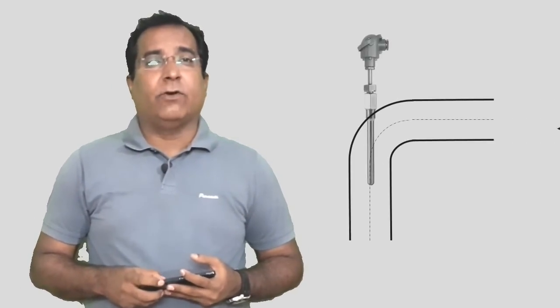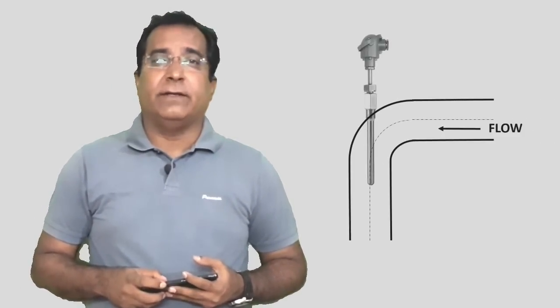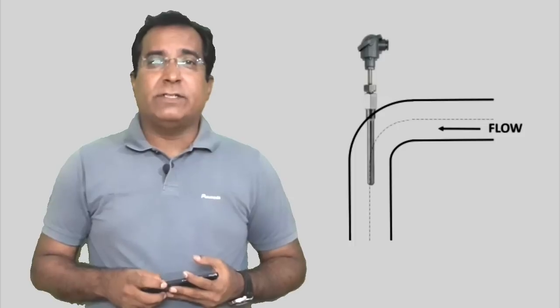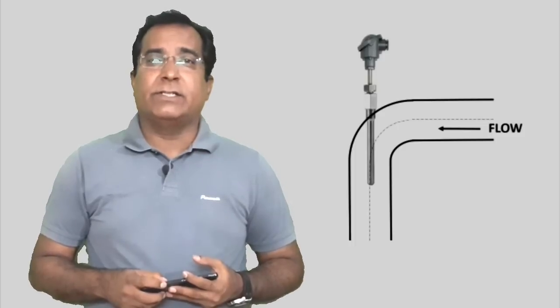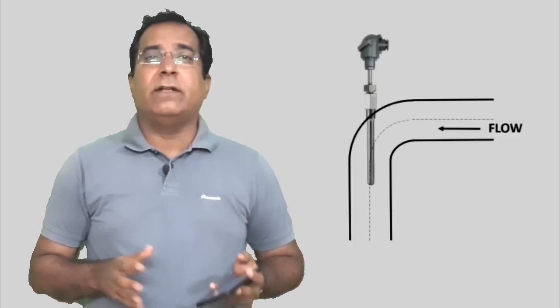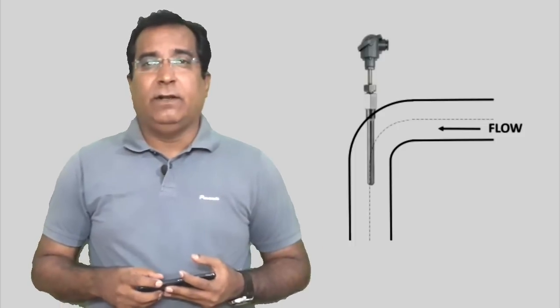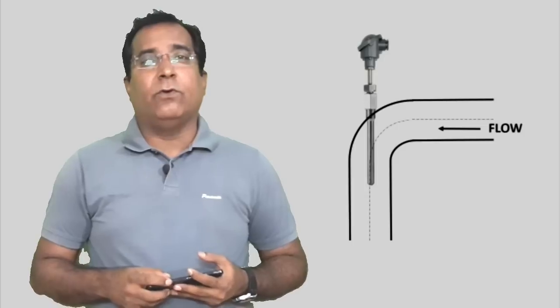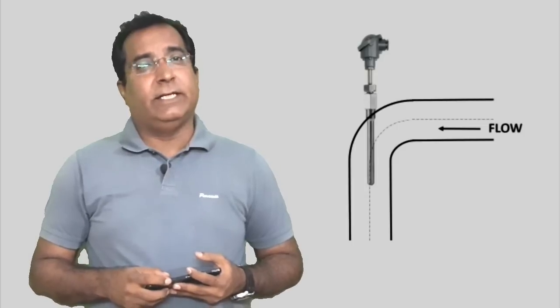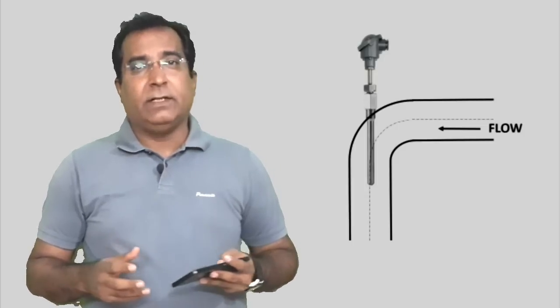If you want the best point in the pipeline to measure temperature, it is the bend portion in the pipeline. Look at the screen. In this way, a turbulence is created in the liquid or gas due to bend, by which the heating media is mixed and gives an average temperature. Also media flow gives the least amount of abrasion due to direction of sheath and flow in the same direction.